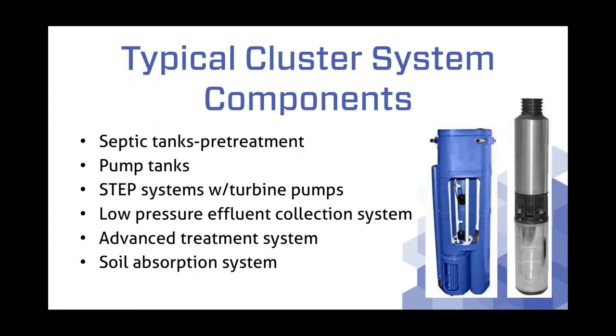Typical cluster system components will involve septic tanks with pretreatment. Oftentimes, because of elevation changes throughout the development, we're going to have pump tanks installed to carry the pretreated effluent to the advanced treatment system and dispersal system. Within these pump tanks, we'll typically use a STEP system with a turbine pump. Pumps will then flow to a low pressure effluent collection system, and then finally to an advanced treatment system for the entire cluster, and then to a soil absorption system for final disposal.